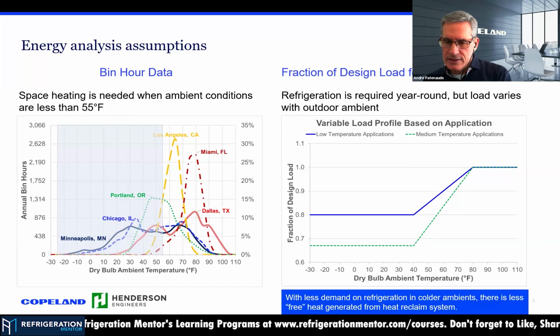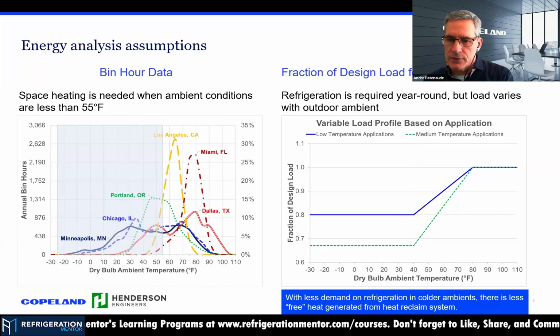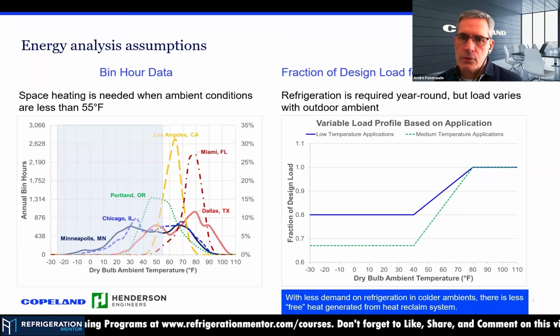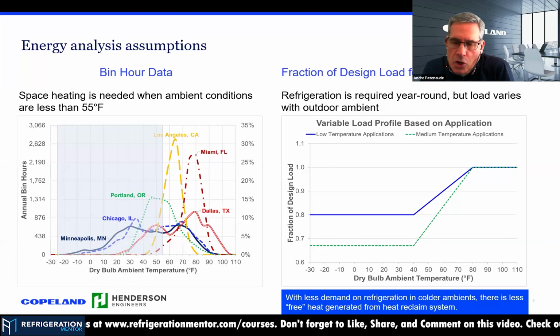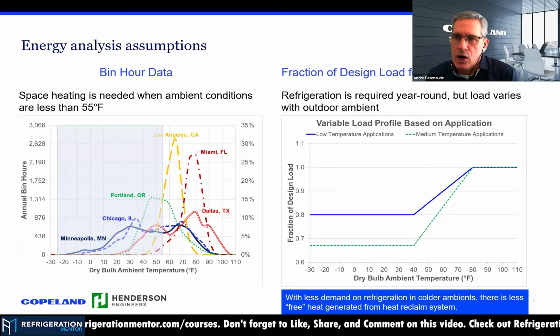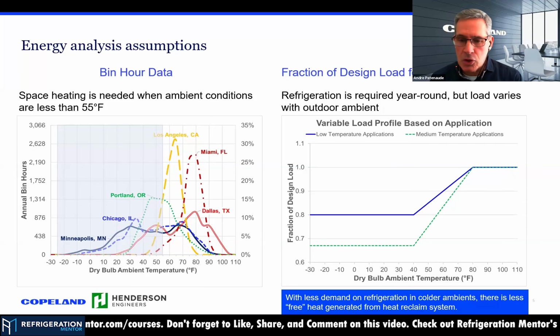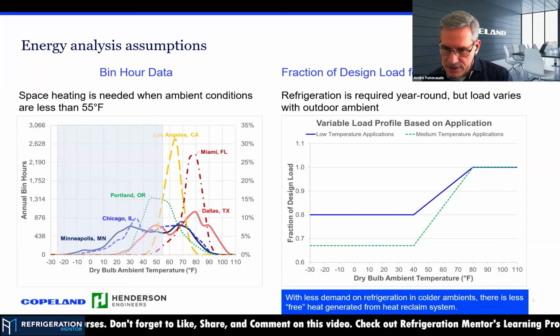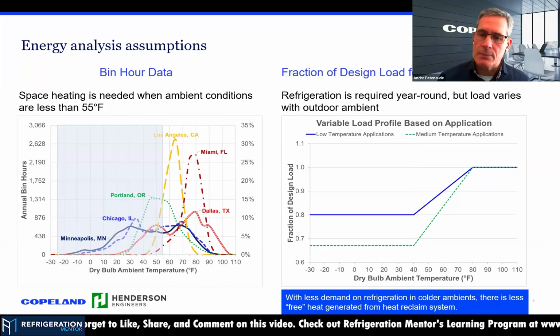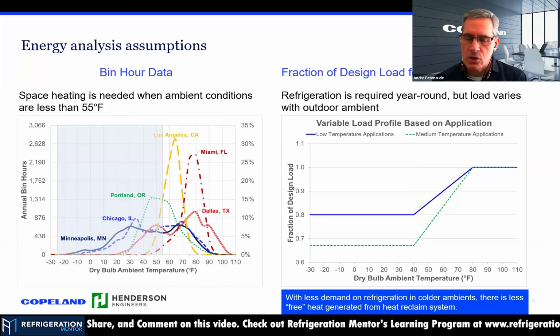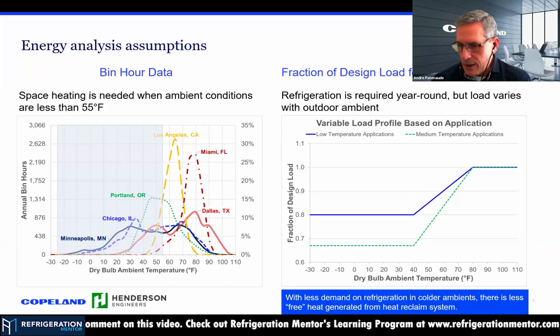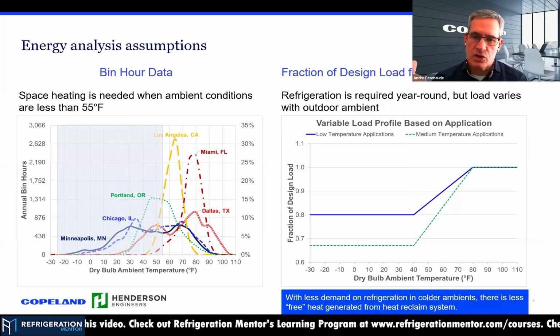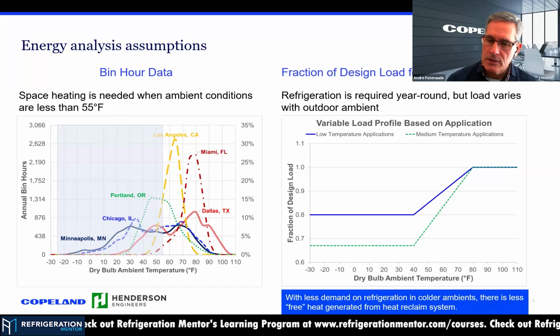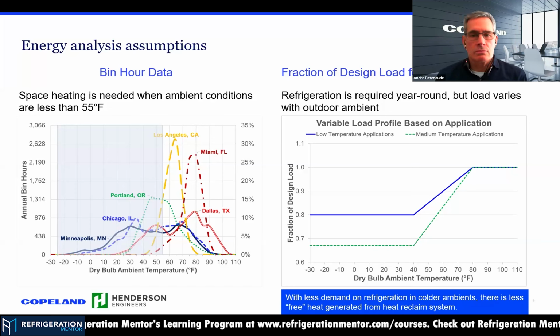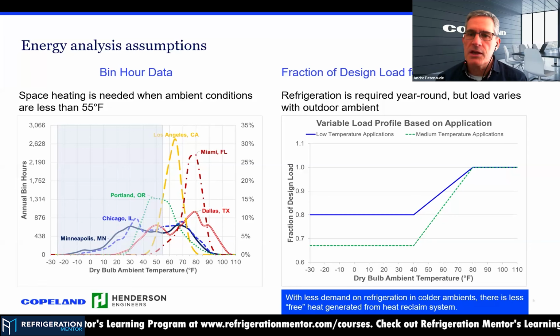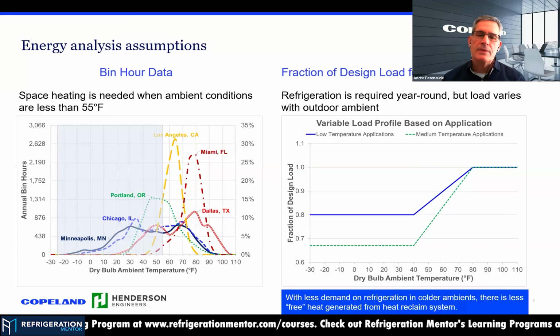The chart on the right, you may have seen this if you use product selection software from Copeland. It's a design load for refrigeration, and we all know that as it gets colder outside, our design load starts to drop. So you can see at around 40-degree ambient, our design load has dropped significantly. So we factored that into our calculations. So our loads are dropping. That means the total heat of rejection available is proportionately dropped. So we can't heat as much, but that's okay. We factored that in so we can understand how much free heat we have available. Okay, that was part of it.